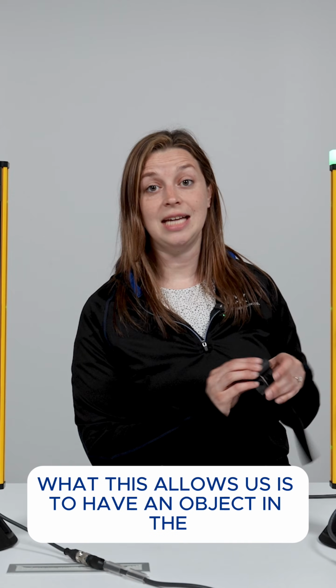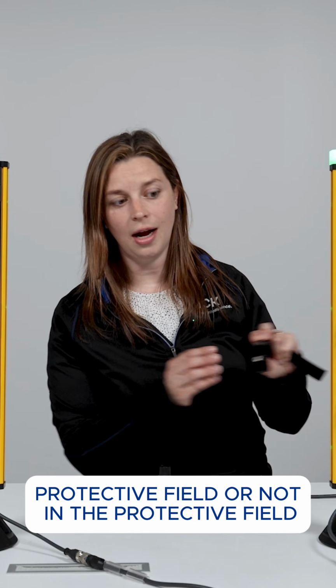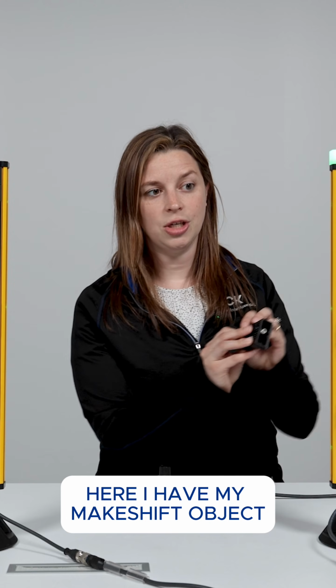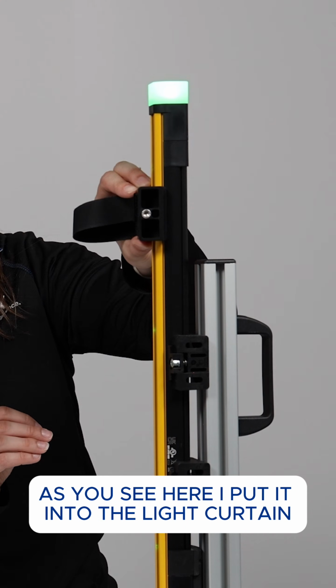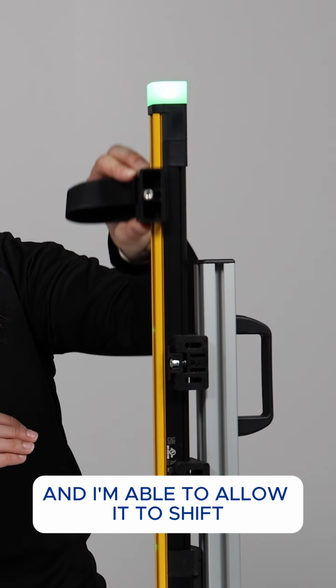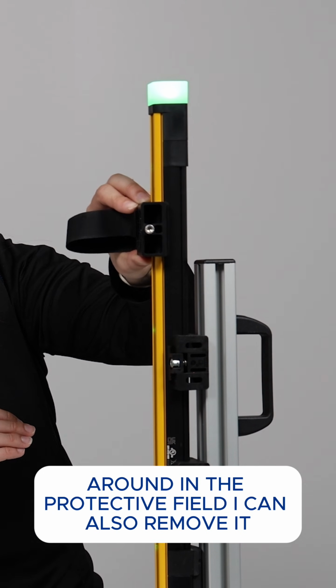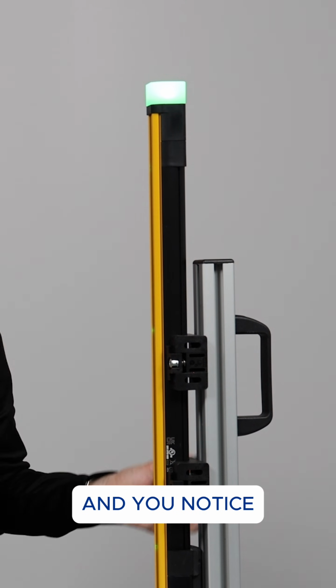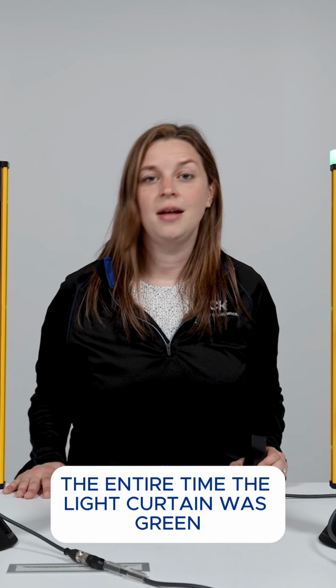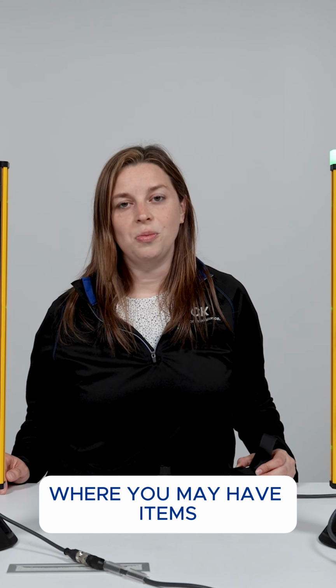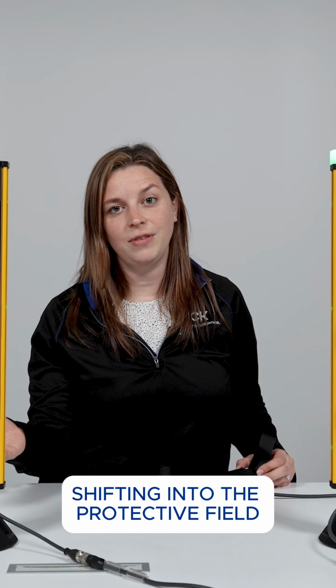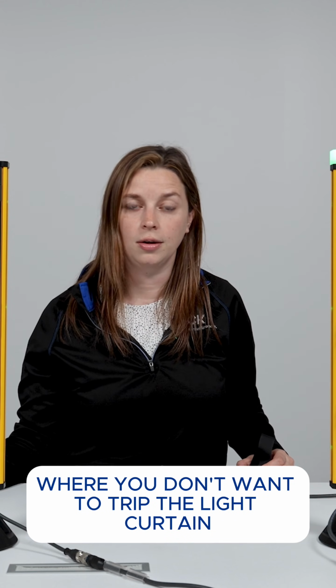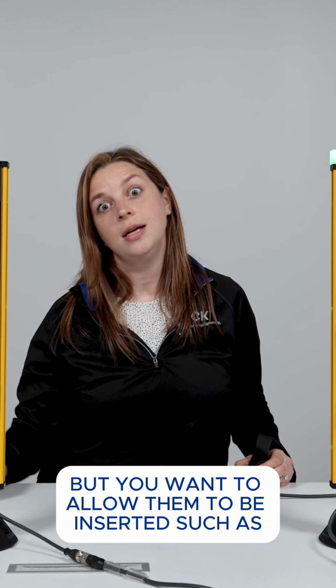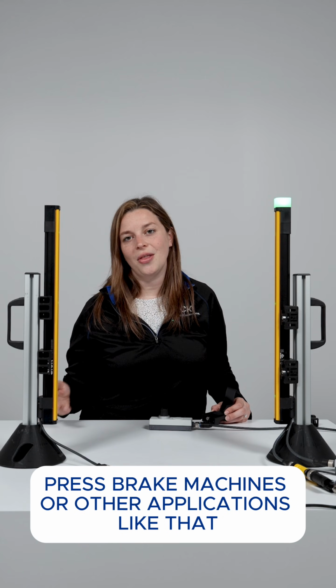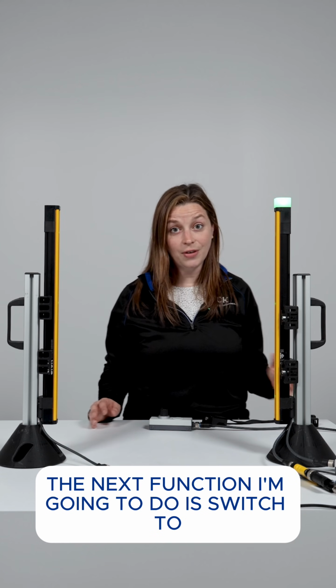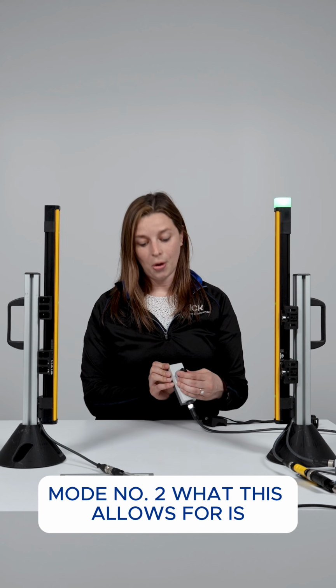What this allows us is to have an object in the protective field or not in the protective field. Here I have my makeshift object. As you see here, I put it into the light curtain and I'm able to allow it to shift around in the protective field. I can also remove it, and you notice the entire time the light curtain was green. This is great for those applications where you may have items shifting into the protective field where you don't want to trip the light curtain, but you want to allow them to be inserted, such as press brake machines or other applications like that.